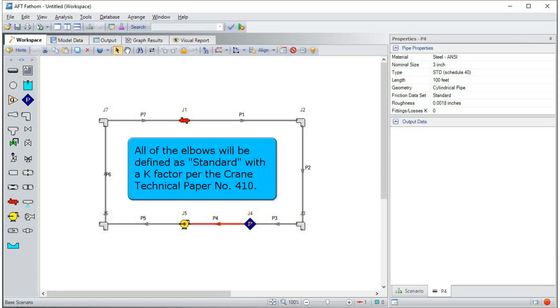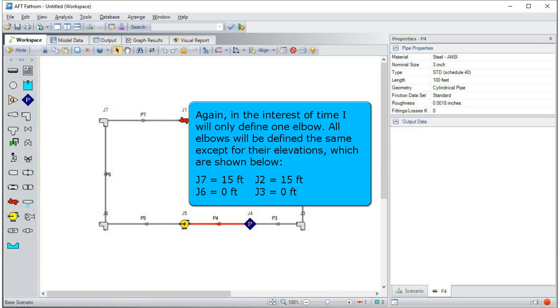All of the elbows will be defined as standard, with a k-factor per the Crane Technical Paper number 410. Again, in the interest of time, I will only define one elbow. All elbows will be defined the same except for the elevations, which are shown below.